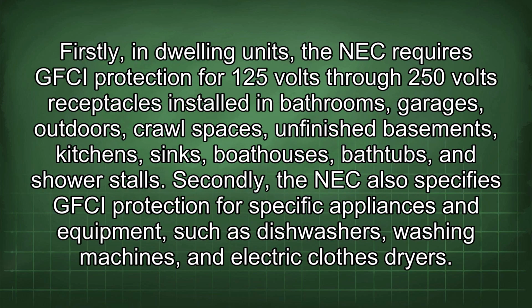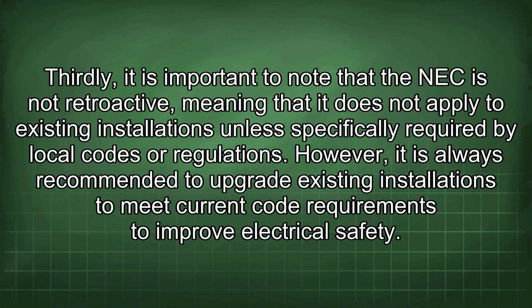Firstly, in dwelling units, the NEC requires GFCI protection for 125 volt through 250 volt receptacles installed in bathrooms, garages, outdoors, crawl spaces, unfinished basements, kitchens, sinks, boathouses, bathtubs, and shower stalls. Secondly, the NEC also specifies GFCI protection for specific appliances and equipment such as dishwashers, washing machines, and electric clothes dryers. Thirdly, it is important to note that the NEC is not retroactive, meaning that it does not apply to existing installations unless specifically required by local codes or regulations. However, it is always recommended to upgrade existing installations to meet current code requirements to improve electrical safety.